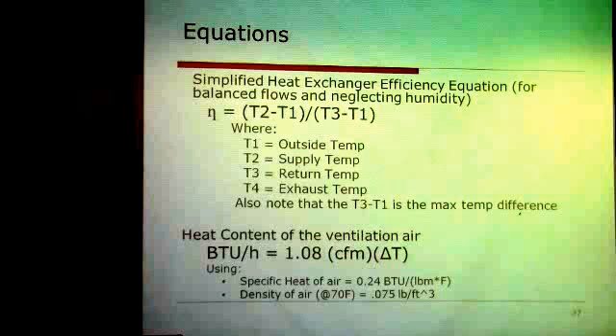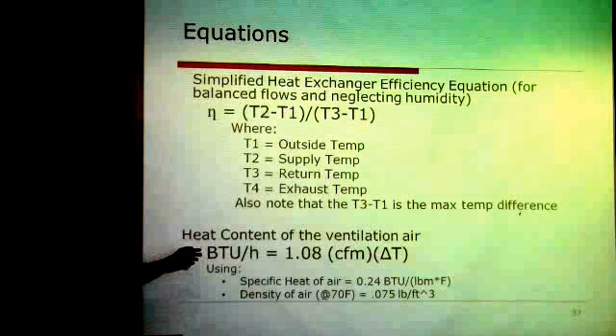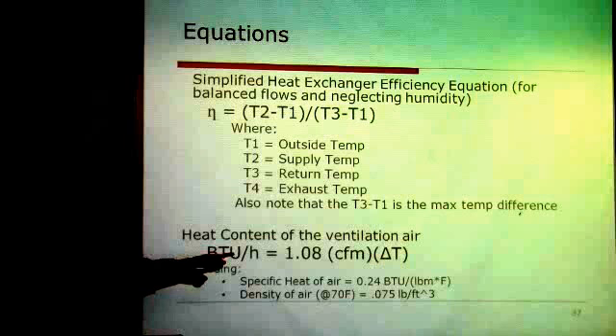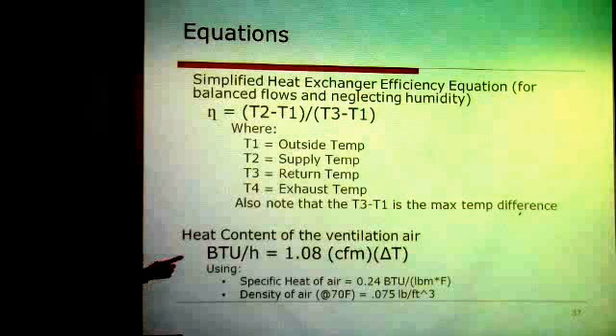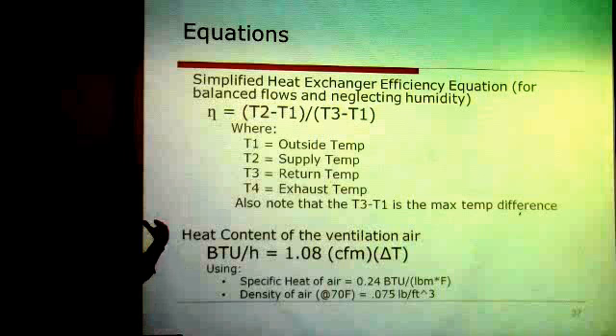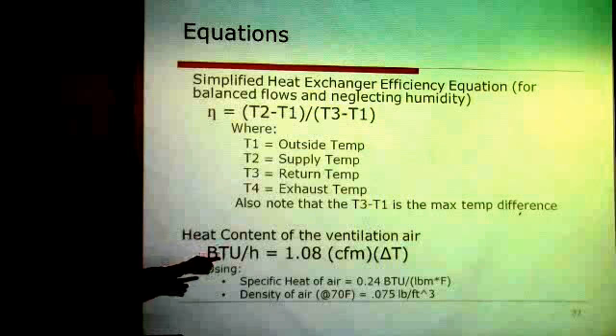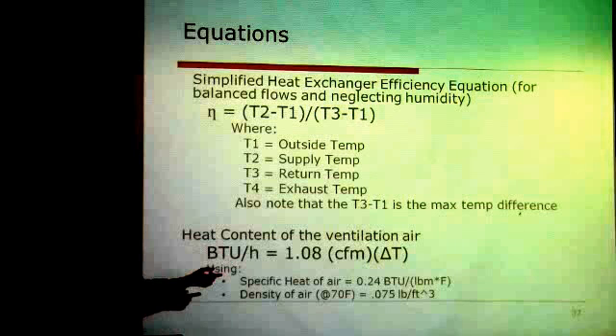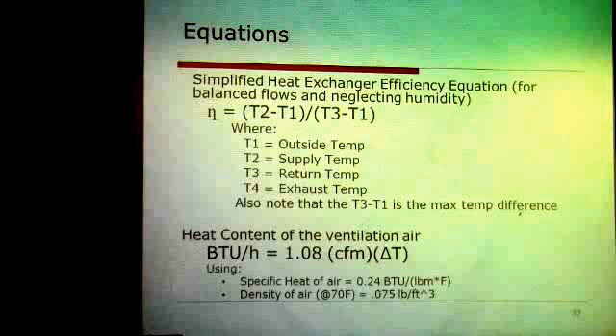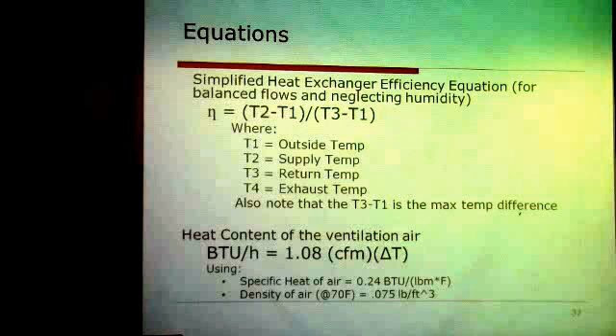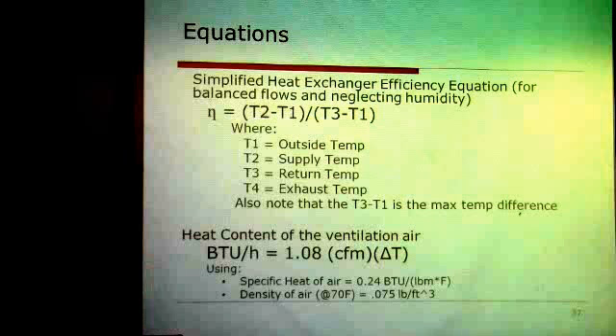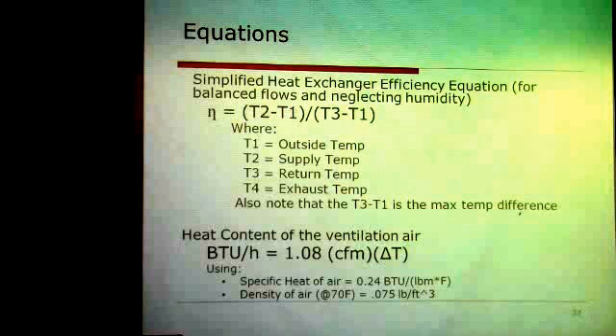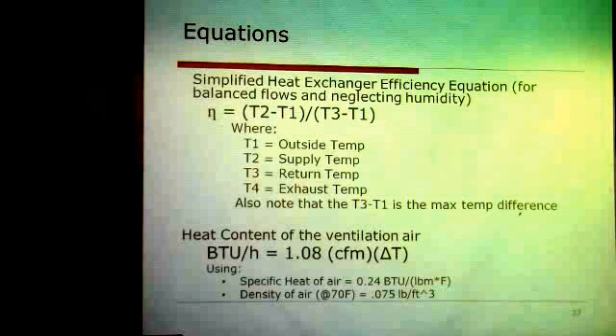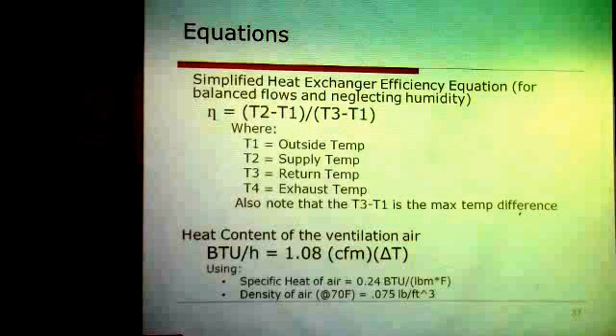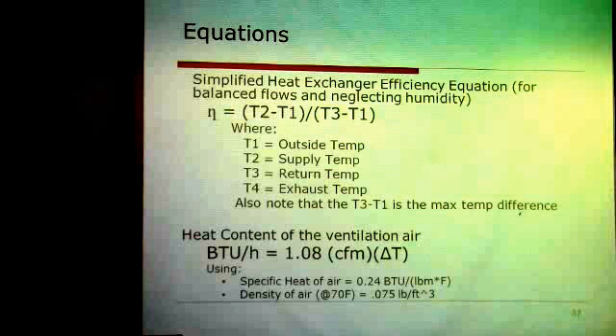Anyway, that formula comes in. Also, when you're trying to cool the air, in our early example we said you can get the temperature of the incoming air down to 60 degrees, and then your room temperature is 75, so you're supplying a 15-degree delta temperature into the house. Times your 100 CFM, that would be 1,500 BTUs of cooling times 1.08, so you're still less than 2,000 BTUs of cooling you can supply over this air. So you will get people asking about heating and cooling over the ventilation air. It's not too often done. Some people do it, but you have to be pretty careful with how you do it.